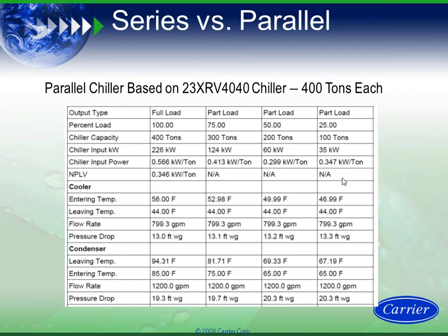So I want to show everybody on the call right now the differences between series and parallel. And I think the best way of showing this is by comparing the exact same chiller by going from parallel flow through the machines to series flow. Now when I go from parallel to series, I have a two-pass typically in a parallel flow plant. When I go to series, I have a single pass. And I'm going to single pass because I don't want to take the pressure drop penalty hit.